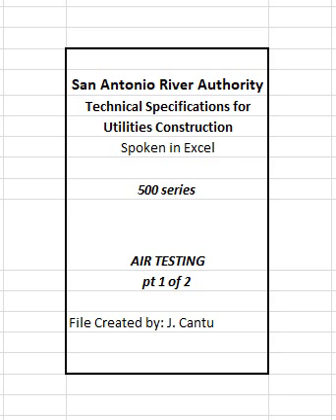518.2 Materials for air testing. 1. A compressor capable of providing at least 300 cubic feet per minute, CFM, at 100 pounds per square inch, PSI, shall be furnished by the contractor. 2. Plugs, valves, pressure gauges, air hose, connections, control panel and other equipment necessary to conduct the air test shall be furnished by the contractor.